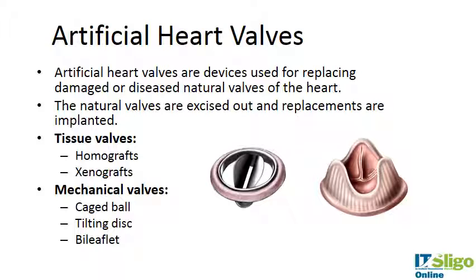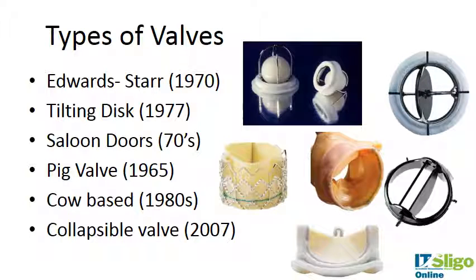An artificial valve is used for replacing the damaged or diseased valve — the natural valve is excised and the replacement is then implanted. They are usually grouped into tissue valves or mechanical valves. Tissue valves shown here are usually porcine or bovine in nature, and can be homografts using the patient's own cells or xenografts from another animal source. Mechanical valves include different types: caged ball was one of the first, followed by tilting disc and bileaflet. The ball-and-cage Edwards Starr valve from the 1970s works by the ball stopping blood flow under back pressure, then lifting to allow flow.